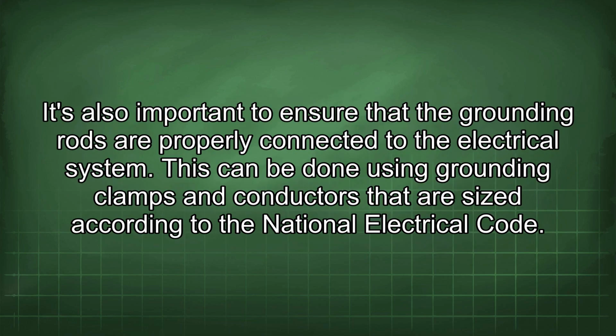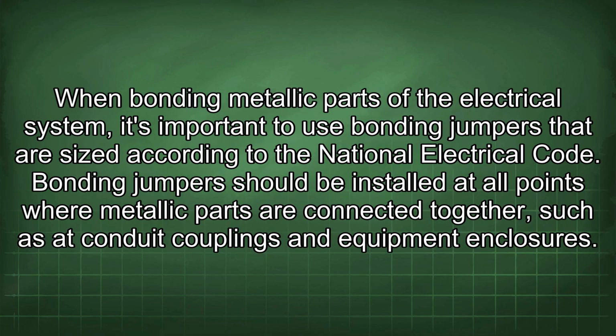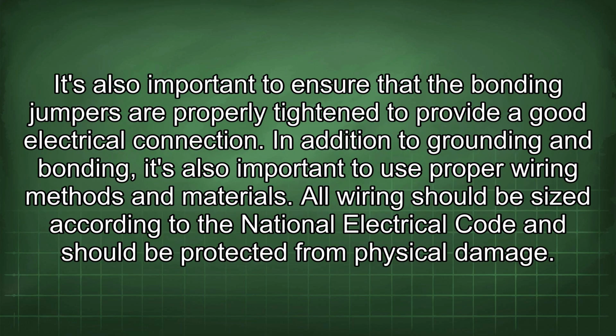It's also important to ensure that the grounding rods are properly connected to the electrical system. This can be done using grounding clamps and conductors that are sized according to the National Electrical Code. When bonding metallic parts of the electrical system, it's important to use bonding jumpers that are sized according to the National Electrical Code. Bonding jumpers should be installed at all points where metallic parts are connected together, such as at conduit couplings and equipment enclosures. It's also important to ensure that the bonding jumpers are properly tightened to provide a good electrical connection.